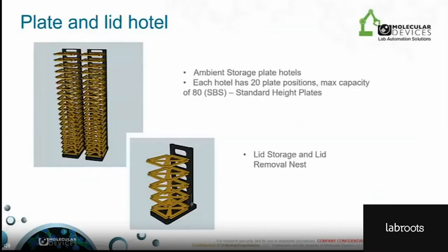For assays that do not require environmental control, plate hotels can be used to store plates required for your application. One plate hotel provides ambient temperature storage for up to 20 plates and can be added over time to accommodate increased throughput needs. Assays that require a lidded plate can be done on an automation work cell by including a lid storage with at least four locations for removed lids and one location for the lid removal action. If your assay requires sealed plates rather than lids, a plate sealer and desealer can be integrated into the work cell.